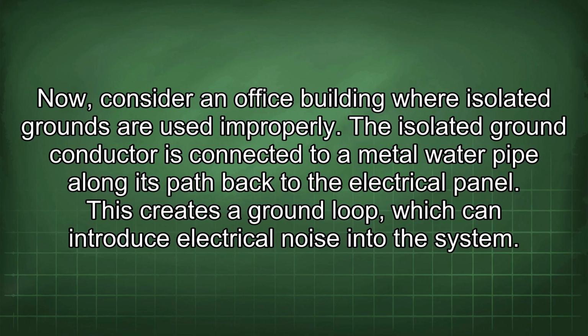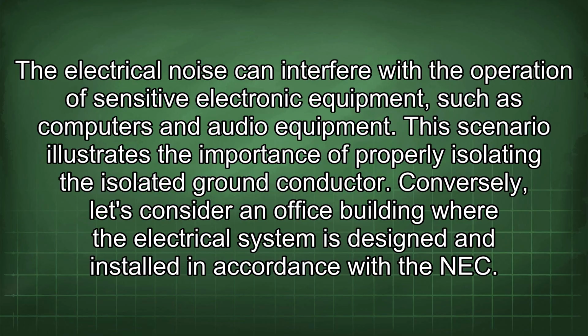Now consider an office building where isolated grounds are used improperly. The isolated ground conductor is connected to a metal water pipe along its path back to the electrical panel. This creates a ground loop, which can introduce electrical noise into the system. The electrical noise can interfere with the operation of sensitive electronic equipment, such as computers and audio equipment. This scenario illustrates the importance of properly isolating the isolated ground conductor.